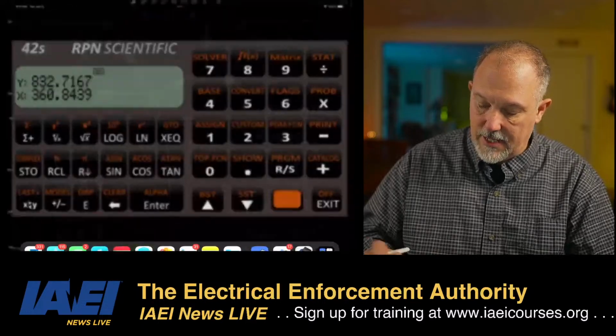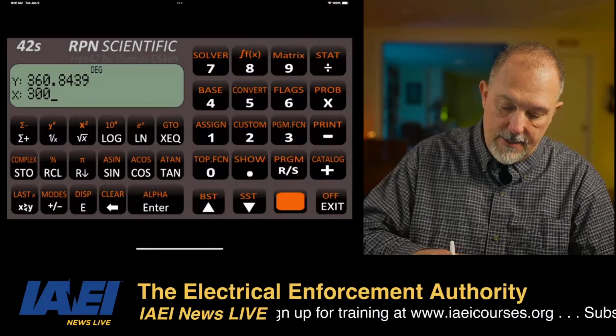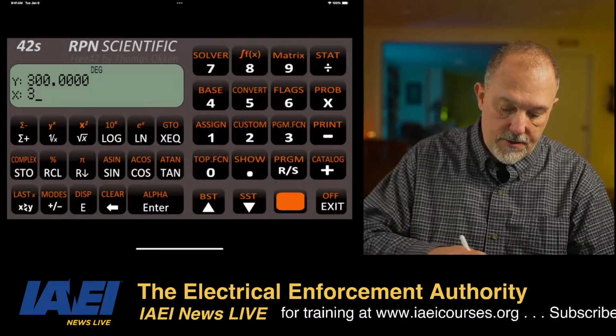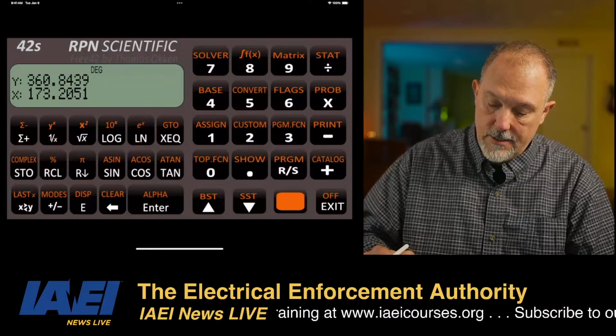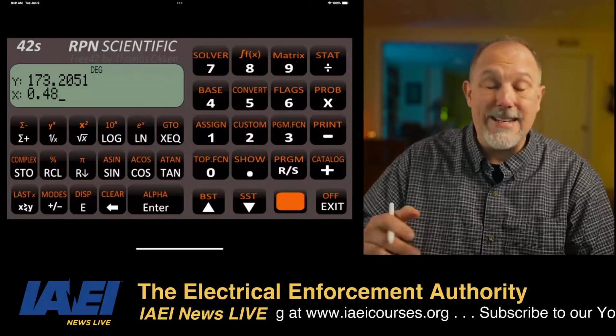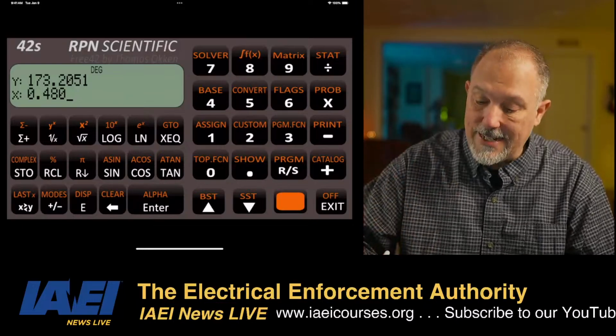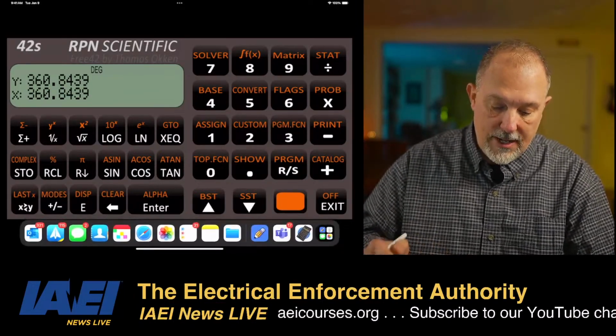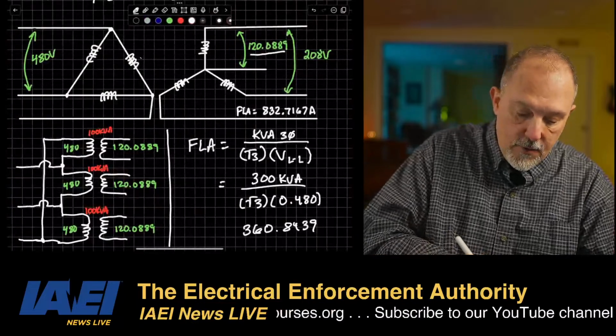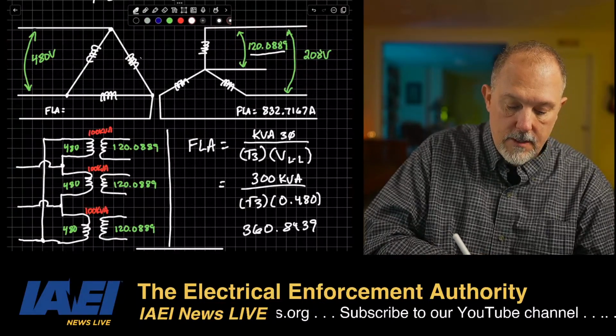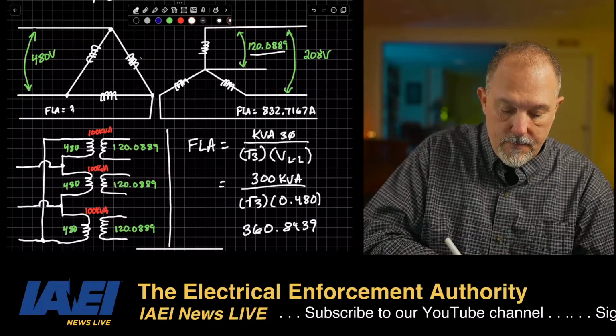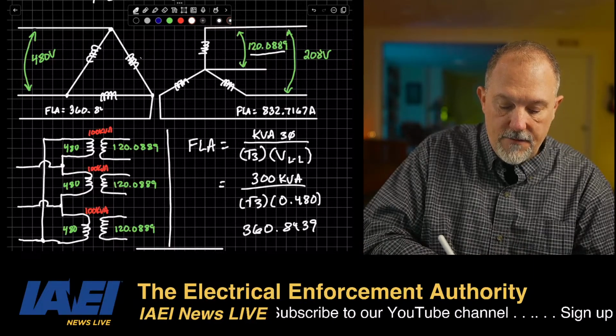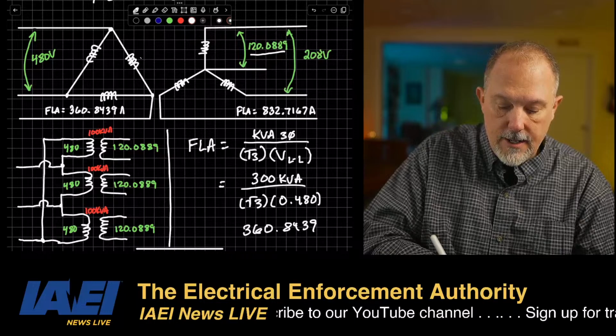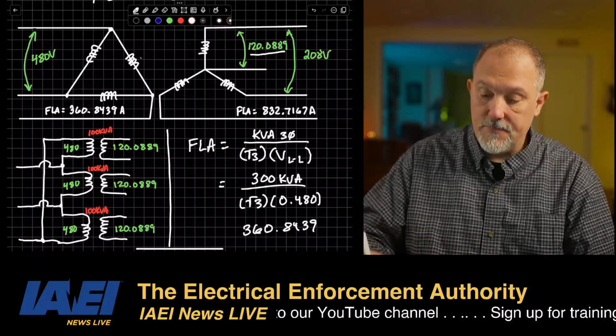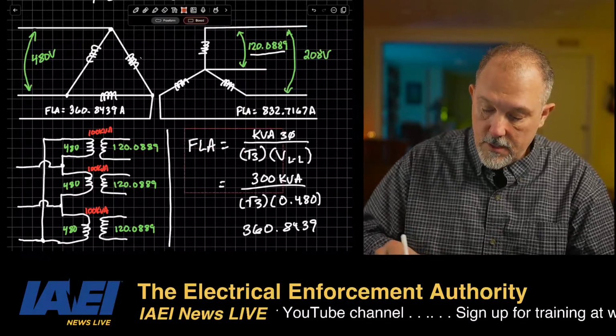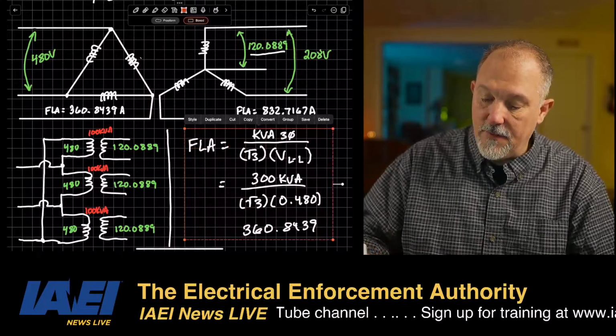Let's do that math again. 300 kVA, the square root of 3, divide 0.480, that's 0.48 kilovolts, 360.8439. So my full load amps over here, 360.8439 amps. All right, so now we have our full load amps.